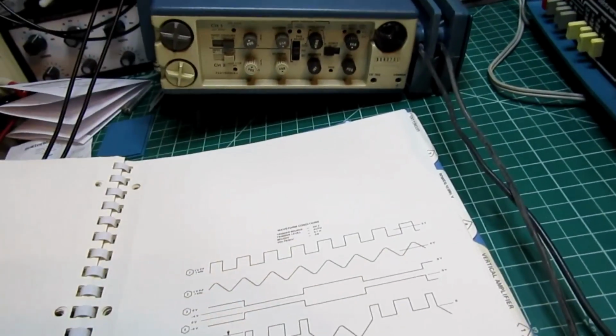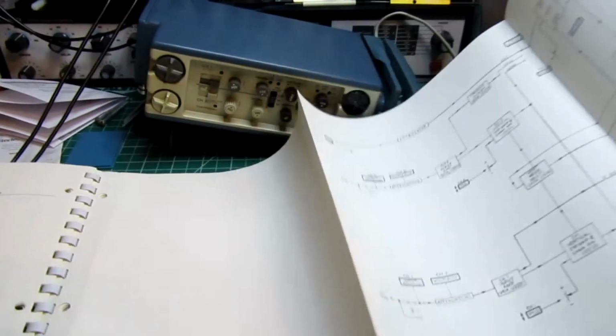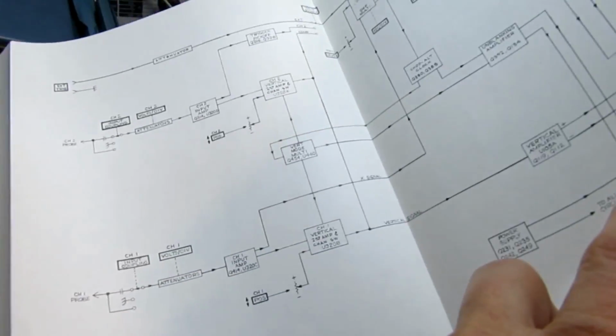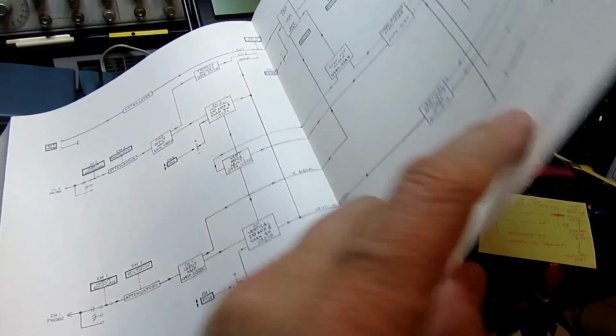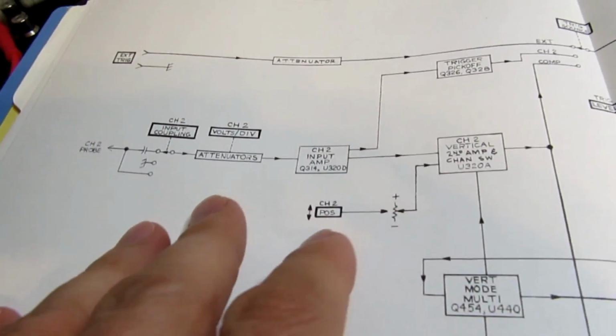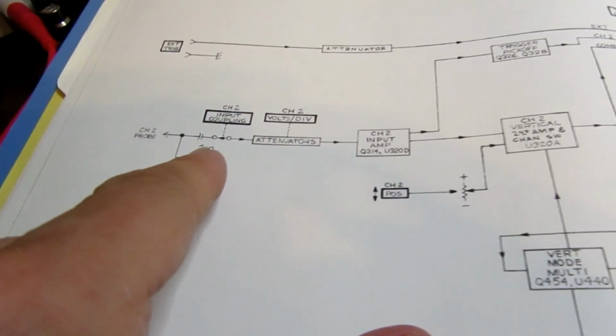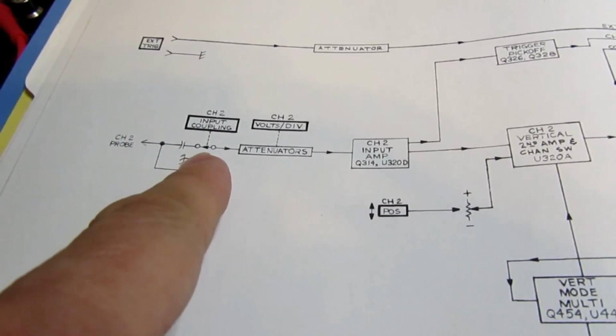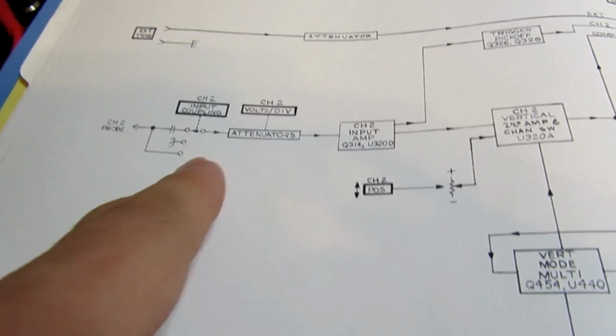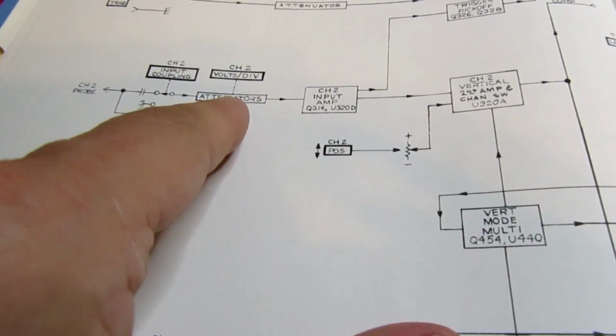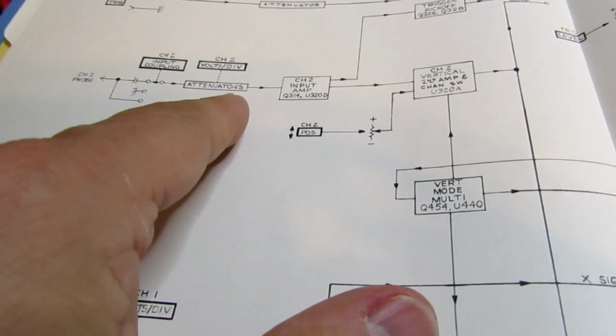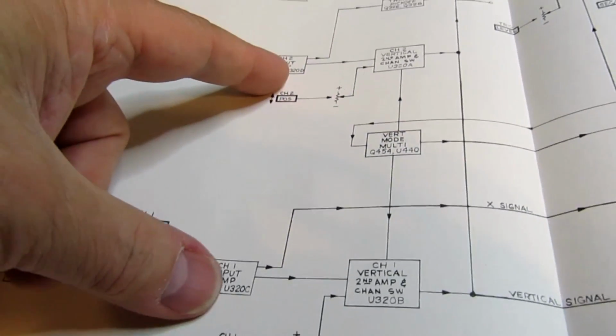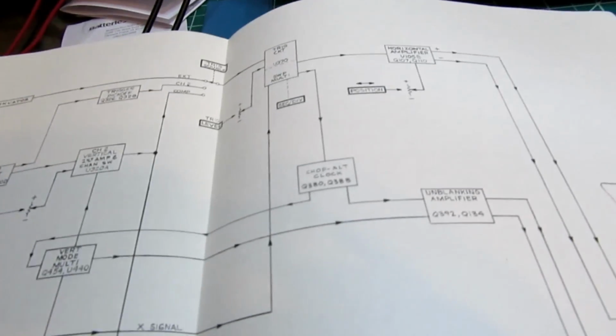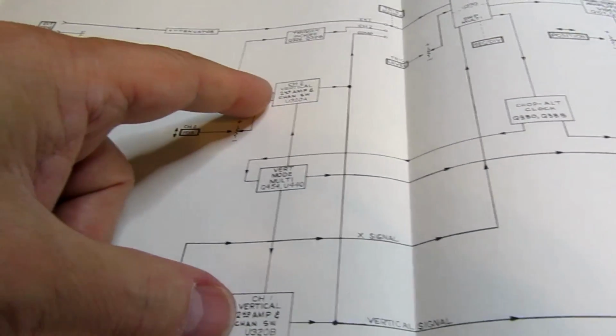So let's see here. This is what I'm looking for. And tech manuals are always good for this. They always have the big fold out, so you can be reading the text part and then having a diagram off to the right if it's set up that way. So the block diagram, you've got your usual direct or capacitively coupled or grounded input switch for each channel. Then you've got your voltage per division attenuators. You've got an amplifier for each channel. And then you've got your vertical second stage amplifier.